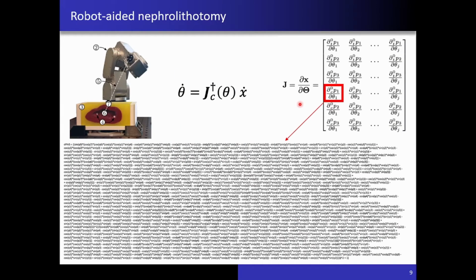Another difference here is that the Jacobian is defined strictly in Cartesian space. X is the position of the tooltip and also the position of point number 7 here, the entry point in the tissue, unlike traditional inverse kinematics where you would have position and orientation. This makes things a lot more complicated. Here is one example of one element in this matrix. There are 58 of those. But this ensures that the joint limits are not saturated and the constraint of always passing through that entry point in the tissue is always respected.